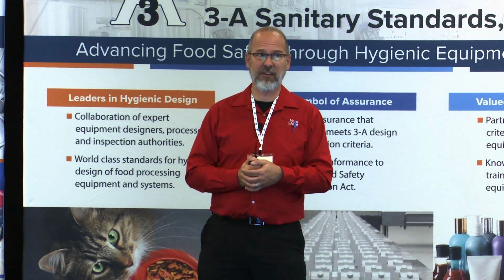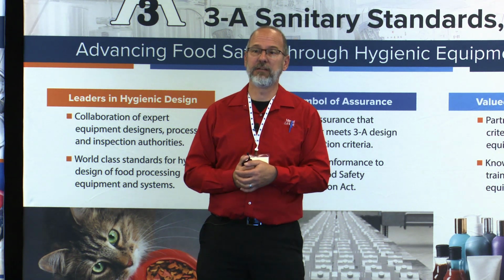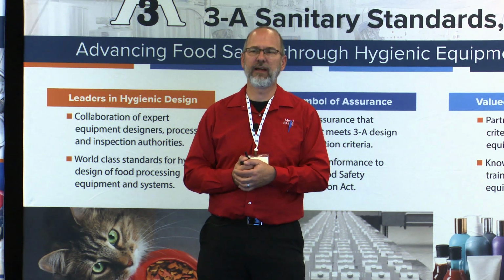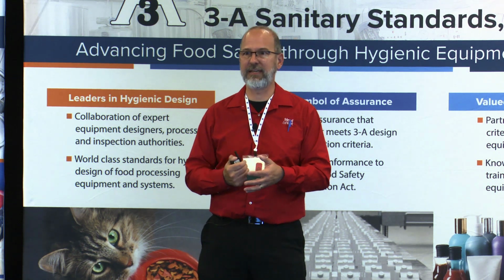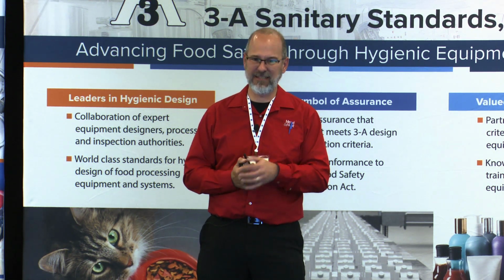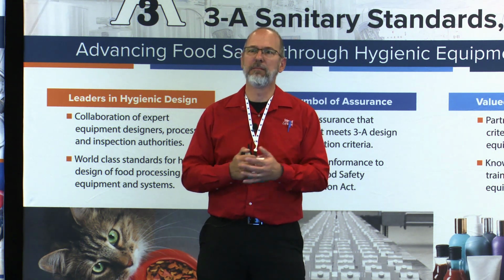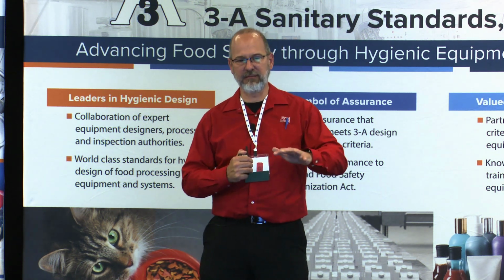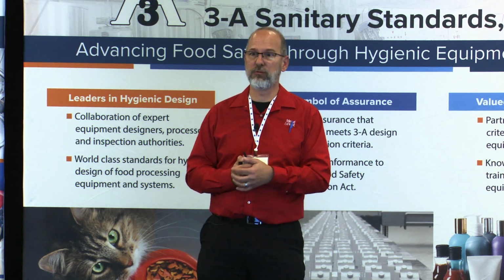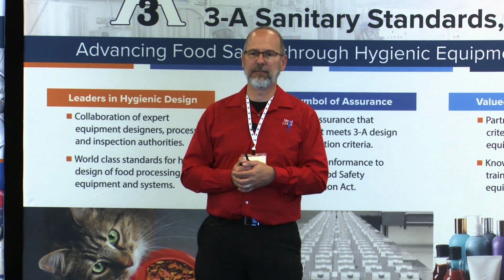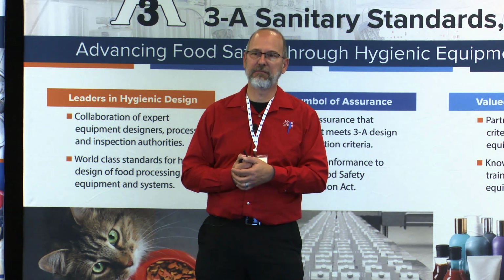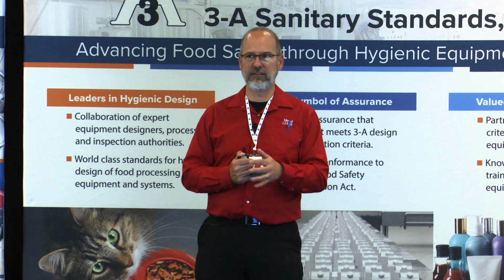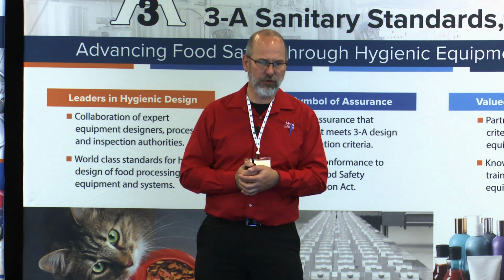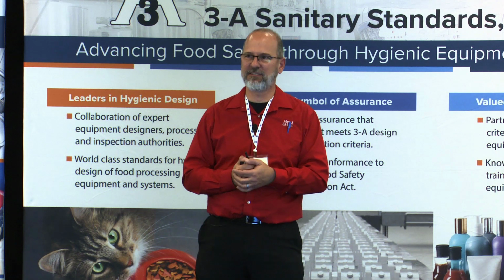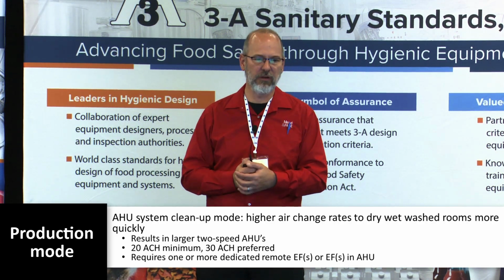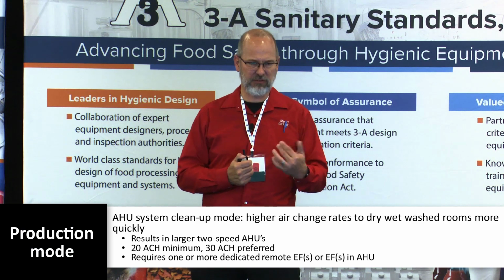Now, if you do need to size to a specific air change rate, you can do that, but you should understand that you're going to end up most likely oversizing your cooling system and then having reheat in a much larger, more complicated air handler to get the exact conditions you want. So it can be done, but I would just caution people about blindly specifying an air change rate. If you're really trying to dry a room out and air condition it to a set point somewhere below 80, 85 degrees, flat air change rates aren't always the way to go. So if you do need to go that route, be prepared to have extensive discussions with the HVAC engineer you're working with. The other operational mode that I mentioned was cleanup mode.